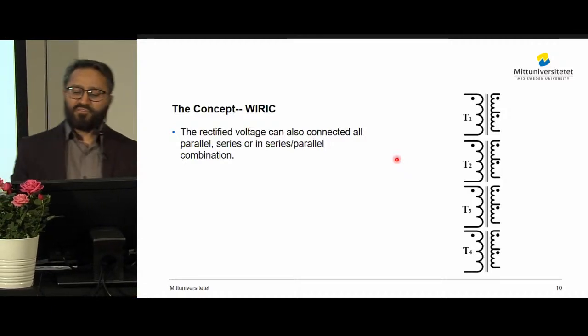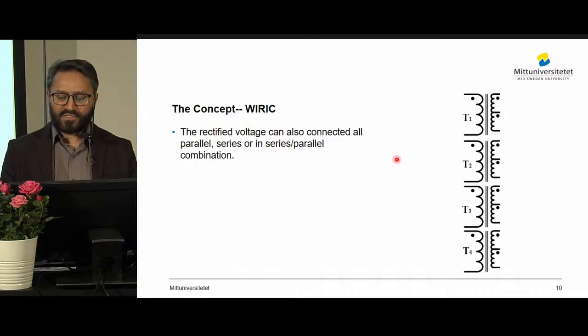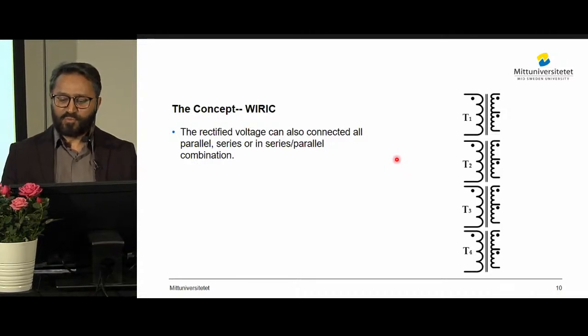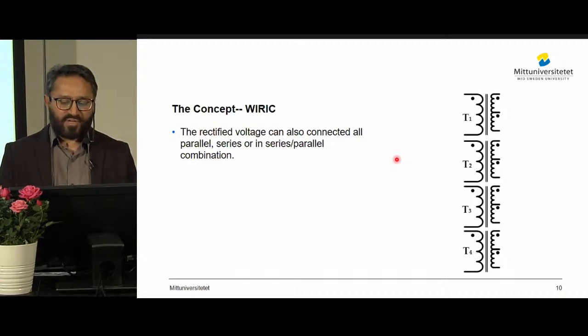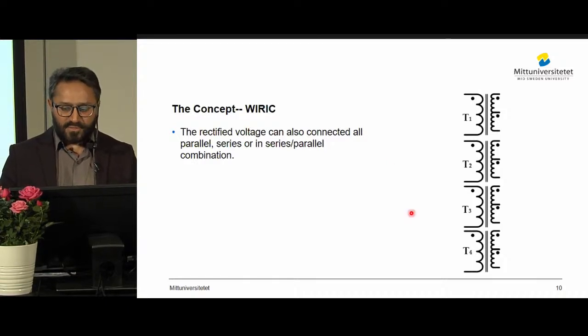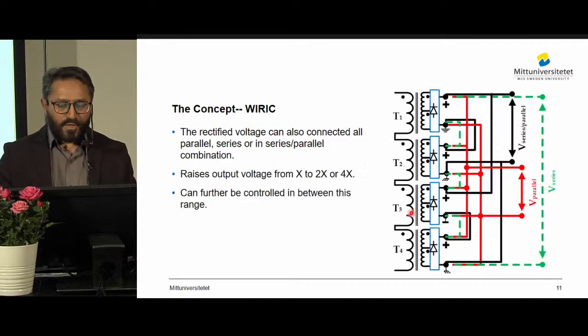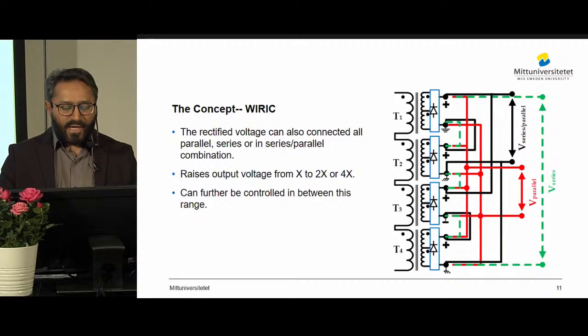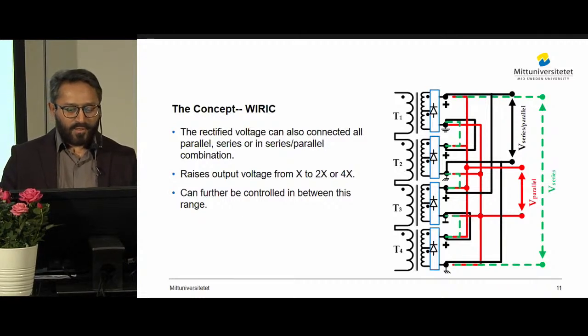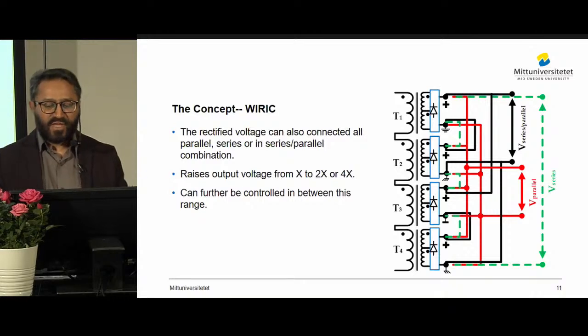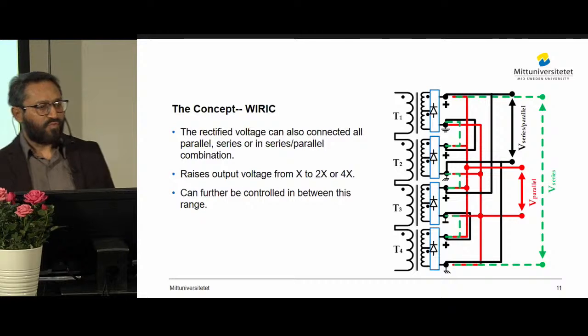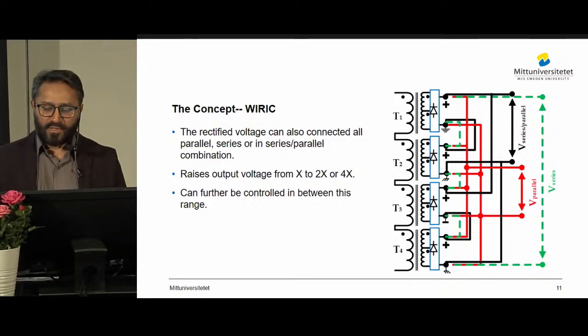Similarly, the provision of more than one transformer also provides the possibility to extend the range of output voltage. After rectification, all 4 transformers can be arranged to connect either all in parallel, all in series, or in a combination of series-parallel connections. In this way, the output voltage can be raised to 4 times the base voltage, and the range can further be extended in between this range.